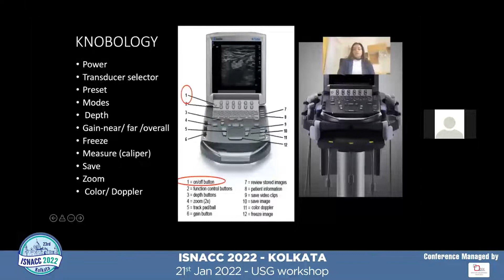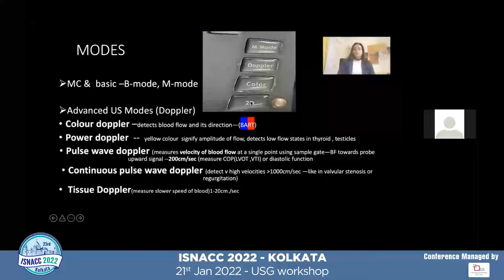Then come the modes. There are 4 keys on the right side of the bottom of the panel. So this is 2D, color, Doppler, and M mode. Color and Doppler are advanced modes. The basic and the most common are 2D and M mode only. So 2D mode is the B mode or the brightness mode. It is the default mode, and whenever you switch on, the machine starts in B mode only. So it gives anatomic representation of the structure. This is the standard imaging modality of ultrasound, and there are 2 dimensions here, width and depth. This is the horizontal axis, and this is the vertical axis, and the structures closer to the probe will be closer to the top of the screen, and vice versa.